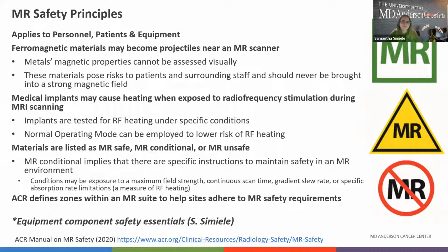Once we're happy with the information in the IFU, we will sterilize our equipment and we individually pack each piece of equipment in a peel pack. One of the reasons we do this is we will take a hand magnet prior to going into any procedure, and we will test each piece of equipment as a sanity check, and we will label each piece as either MR safe, MR conditional, which would be based off of the IFU information, or MR unsafe. On the day of the procedure, we then hand this equipment over to our colleagues in imaging physics, and they do a final scan using a hand wand of each piece of equipment. During the procedure, we have a very systematic process of doing a timeout prior to each scan. We keep track of every piece of equipment going into the OR suite as well as coming out.